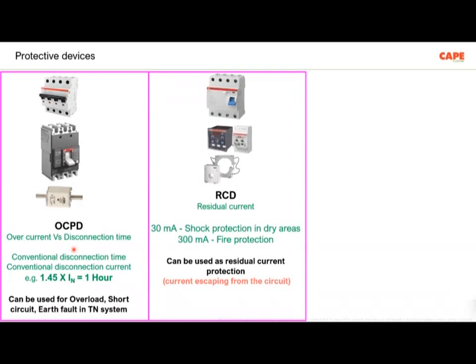Here, what you should understand is the disconnection current. The maximum allowed disconnection current is 30 milliampere. That means if there is a leakage of more than 30 milliampere, the RCD is supposed to trip. 30 milliampere is the shock protection in dry areas. This is the maximum allowed current for shock protection.